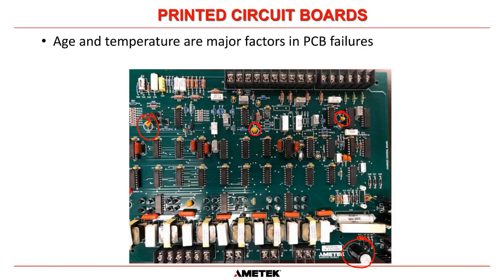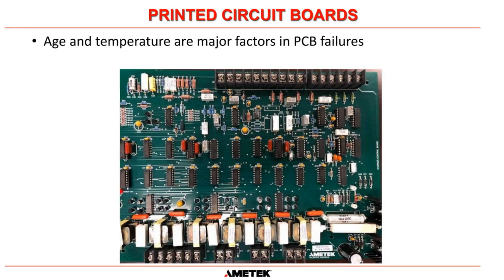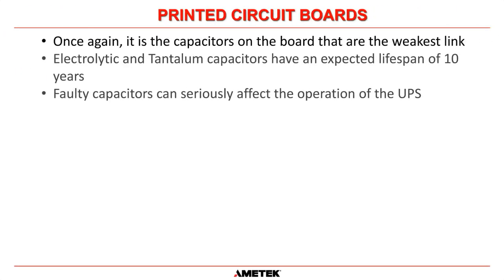So that's why control boards have to be replaced every 10 years, because they have capacitors on them, and any of those capacitors failing can cause misoperation of the PCB and cause the PCB to fail, and therefore the operation of the UPS will probably fail also. The inverter or the charger will shut down, which is definitely not what we want. So if we can stay ahead of the game and perform the maintenance at the regular times, we can prevent those capacitors from failing.